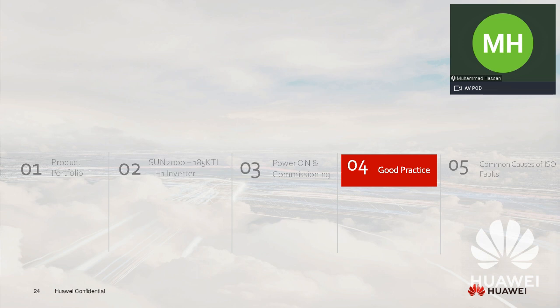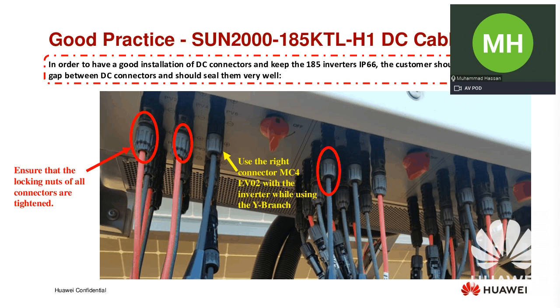Also, coming back to good practice, this is very important, guys, that you need to see and follow the recommendations from us. Here, as I mentioned before, the DC locking nuts should be locked properly, because customers don't buy the proper wrench tool and try to tighten the nuts by hand, so they keep a gap inside. You can see the threads here, which can damage that inverter in future during production, and you will find some faults like ISO faults, because water can go inside, and then you can lose production. So we always advise to lock the nut properly, so there is no thread visible between the locking nut and the connector. It should be properly sealed, so it can maintain the IP66 rating for that inverter.